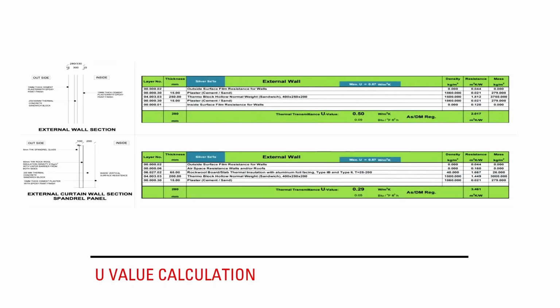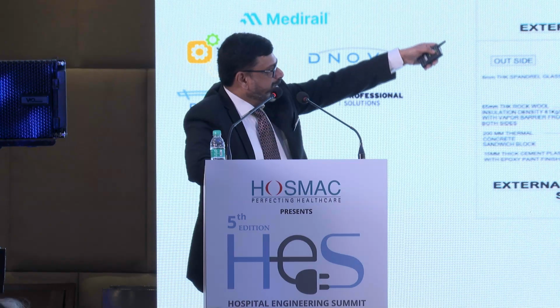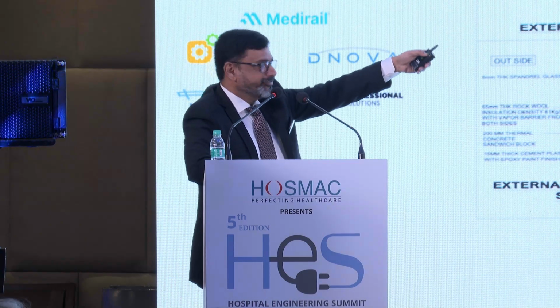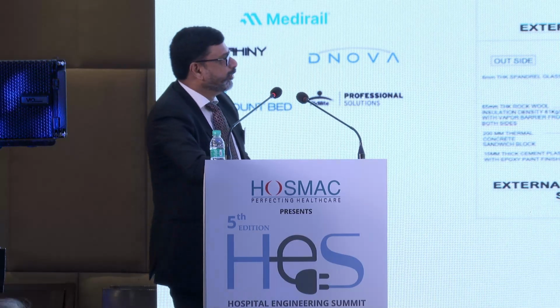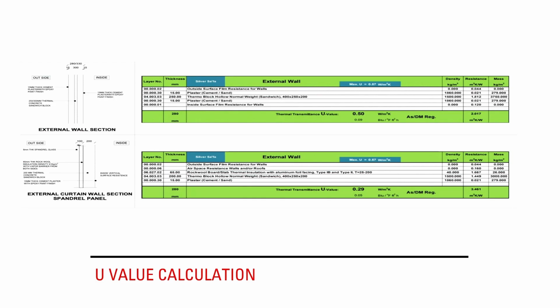Generally, when you look at an external wall, inside and outside, you have a wall with a thickness of cement plaster, insulation material in the middle, and then the internal plaster. Based on that, we calculate the R values, and from the R value you get a U value. In Dubai, we generally have a maximum U value of 0.57, whereas going through India's ECBC documentation, it says 0.4 for some places here, so the requirement for these materials has to be much more stringent to get closer to 0.4.